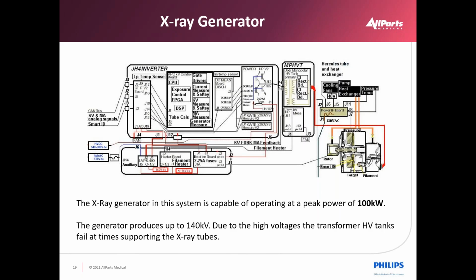In the case of the X-ray generator here, over on the far left, you'll see high voltage DC, anywhere from 540 to 680 volts DC. That's called our DC bus. That drives over to the inverter, which controls changing it into AC. So those inverter controls will then generate AC to drive the high voltage tank to create DC. In this case, this tube uses one high voltage cable, so we're doing a potential of 140,000 volts on just the cathode side. Anode side is grounded.